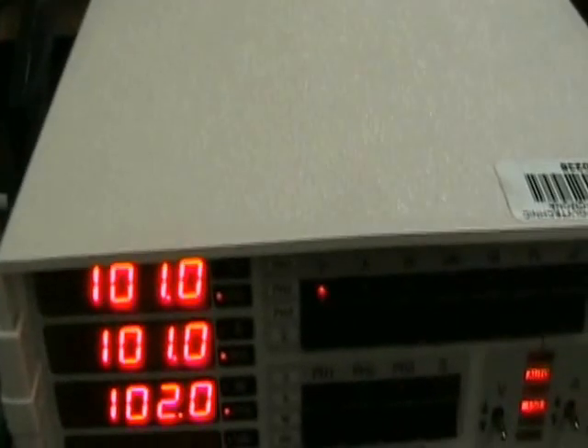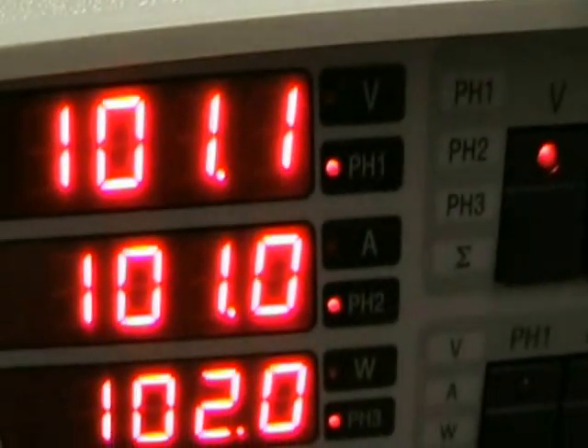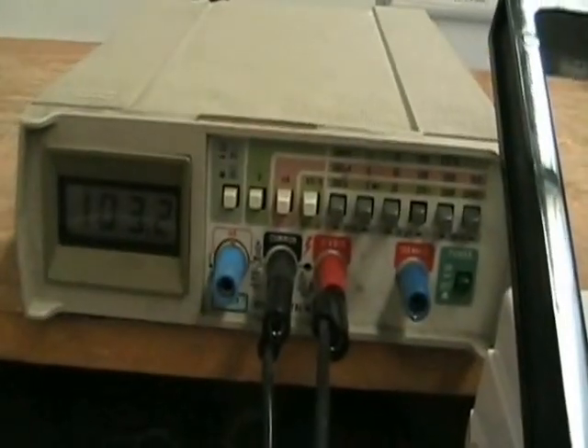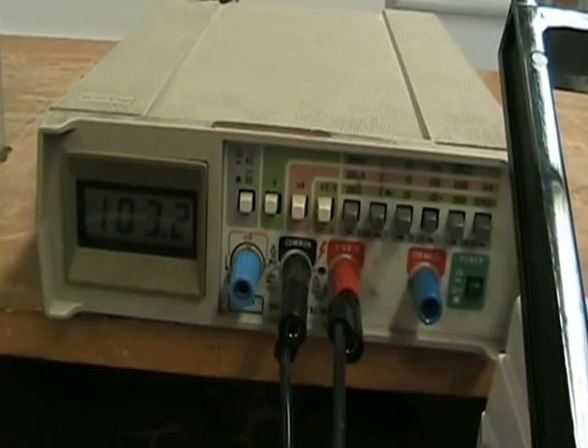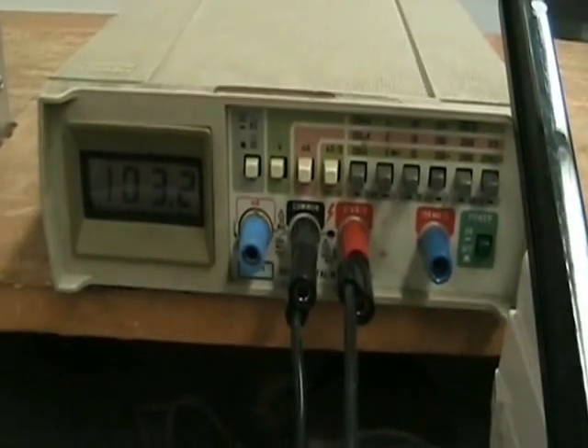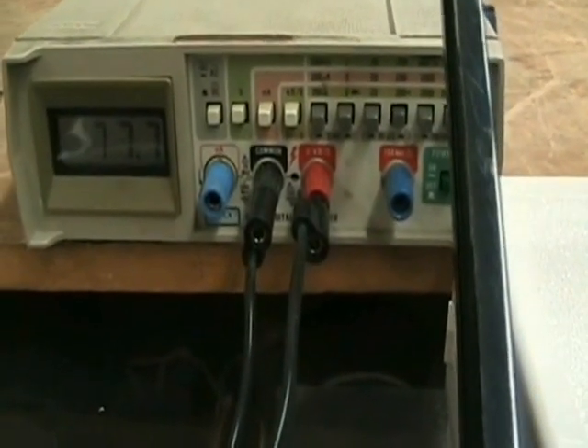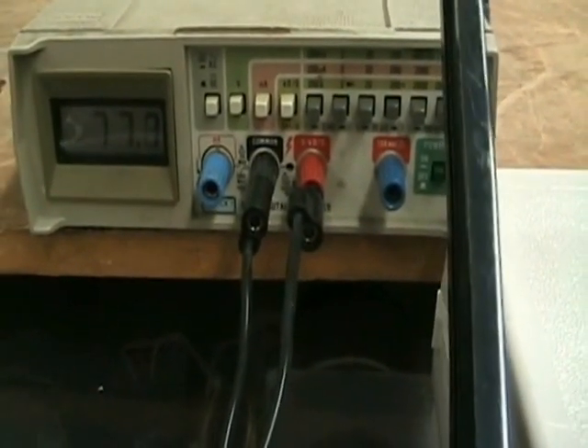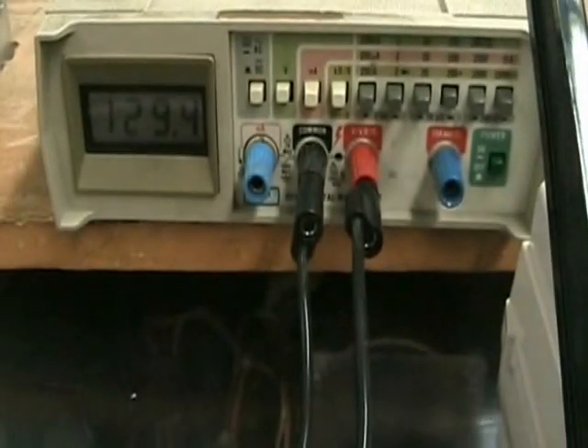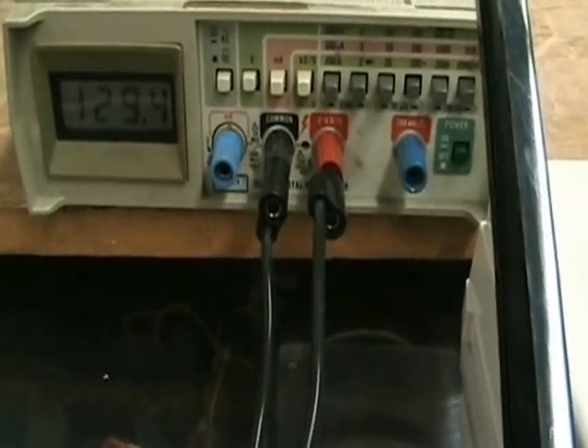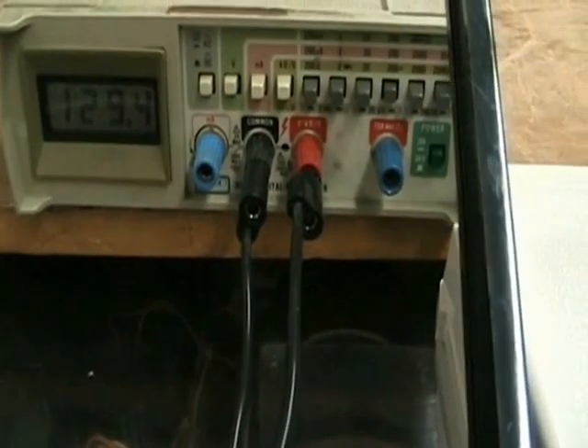Although it is not required, we will indicate the measured phase voltages. At the source, everything is matched. But at the load, we see 103 volts on phase load A, 77 volts on phase B due to the 67 ohm resistance, and finally 129 volts on load C, the 200 ohm load.